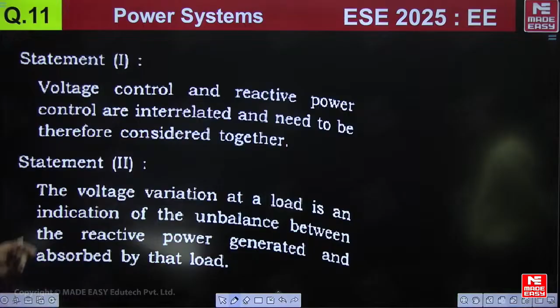Next, question number 11: voltage control and reactive power control are interrelated and need to be considered together. We know that when the load changes, increasing or decreasing, that impacts the reactive power. So control of reactive power is equivalent to control of voltage, and it will cause regulation of the voltage. The voltage variation at a load indicates an imbalance between the reactive power generated and absorbed by that load.